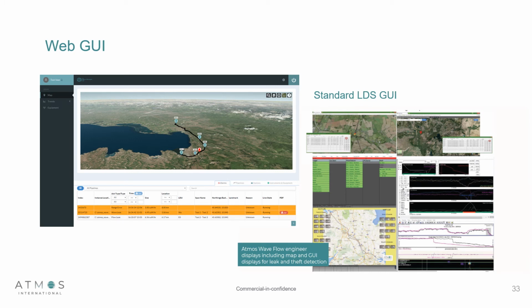And finally, another development is all about how the operator interacts with the leak detection systems and how that information is provided to them. So Atmos utilizes standard leak detection graphical user interfaces that has standard SCADA system screens, utilizes maps to provide the leak location. It has trends so that they can analyze an alarm or have the trends open so that they can monitor the pressure and flows in real time.